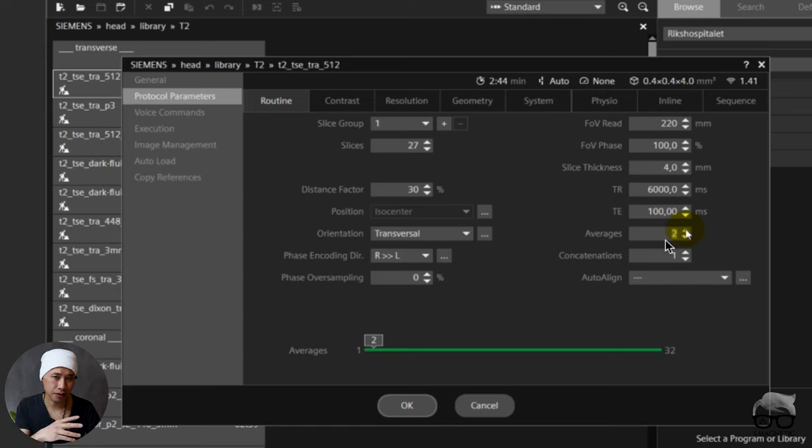And the averages is from 1 to 2, and you see the time will soon increase a lot. See? 5 minutes and 20. So you double the scan time, right? But you only gain a little bit of SNR. But let's check this out. Let's try to double the SNR. So you have to go up 4 times before you get now the double of the SNR. See?